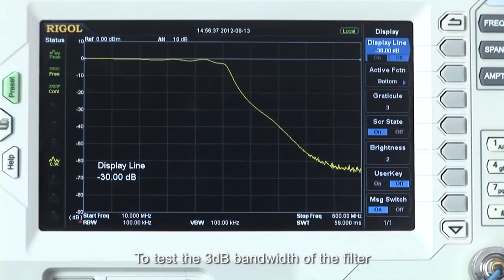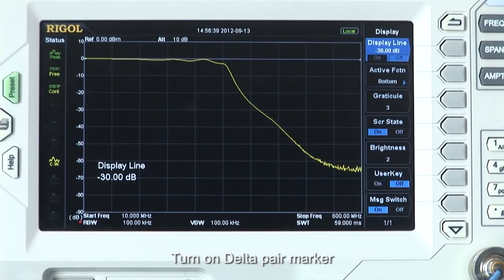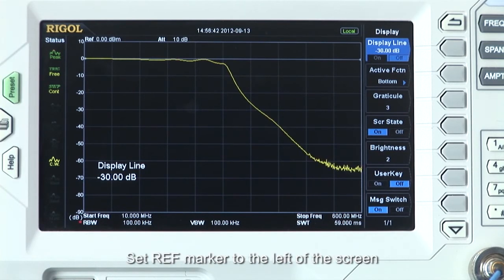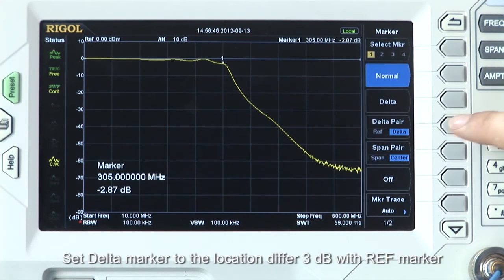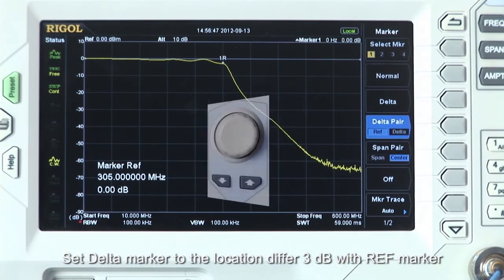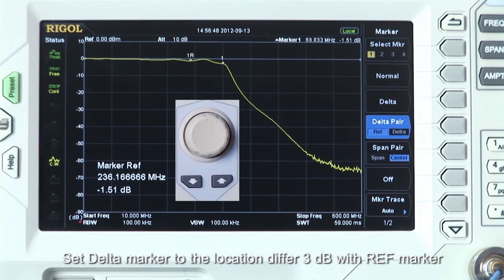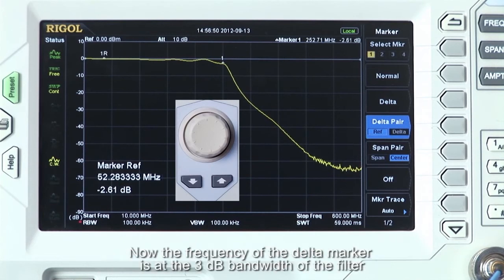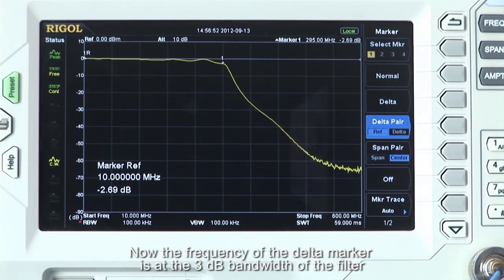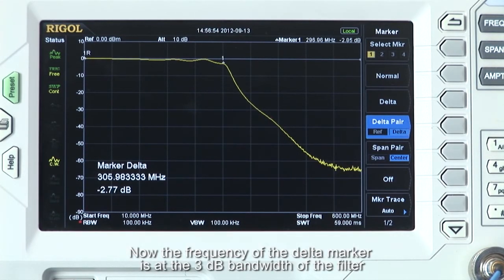To test the 3 dB bandwidth of the filter, turn on the delta pair marker, set the reference marker to the left of the screen, and set the delta marker to the location differing by 3 dB from the reference marker. The frequency of the delta marker is now at the 3 dB bandwidth of the filter.